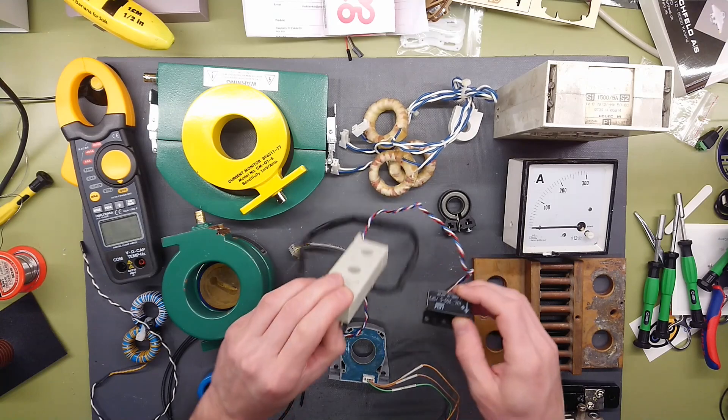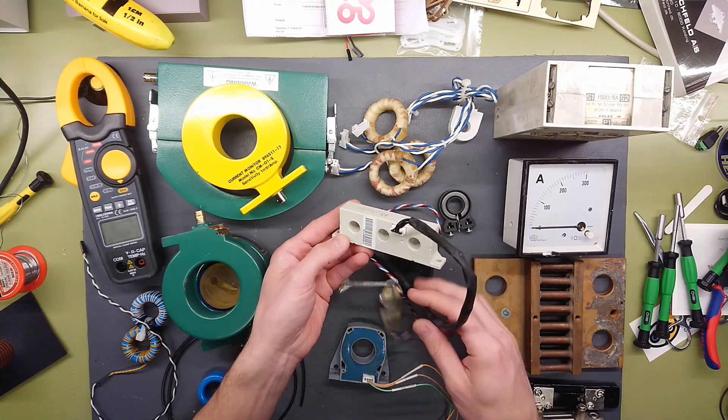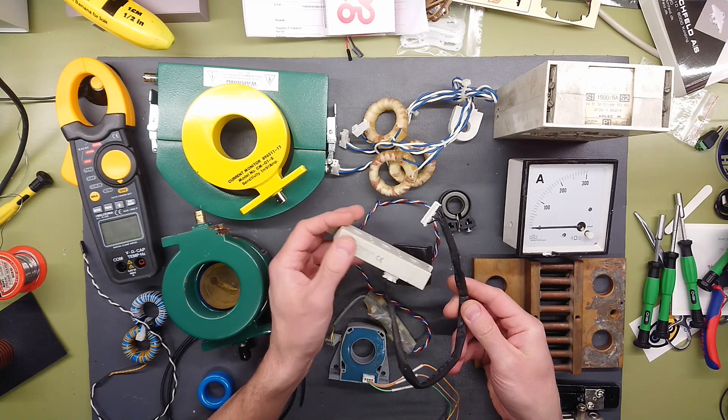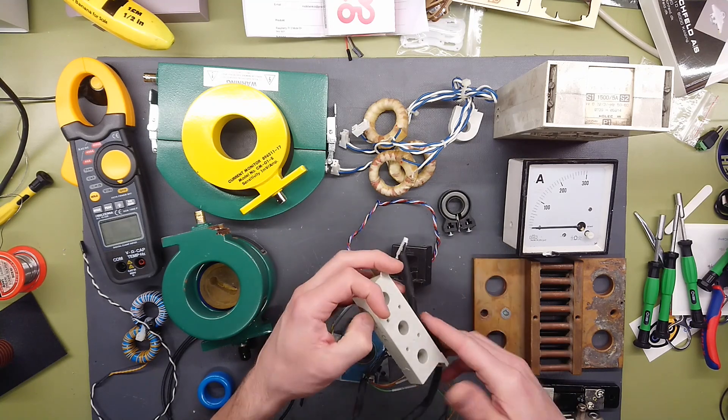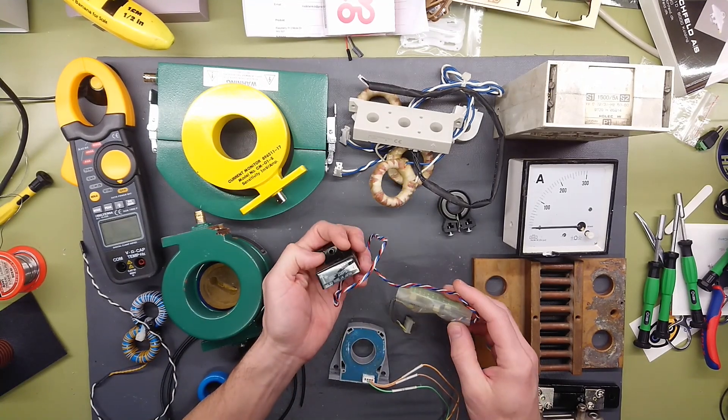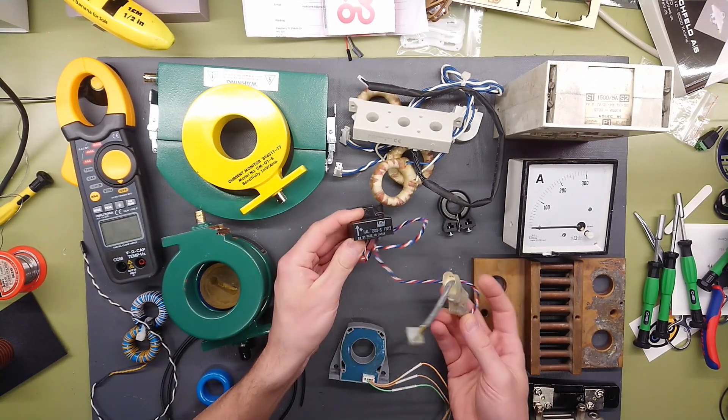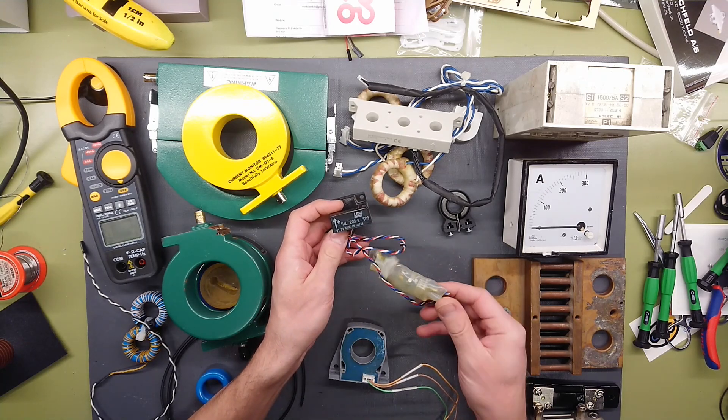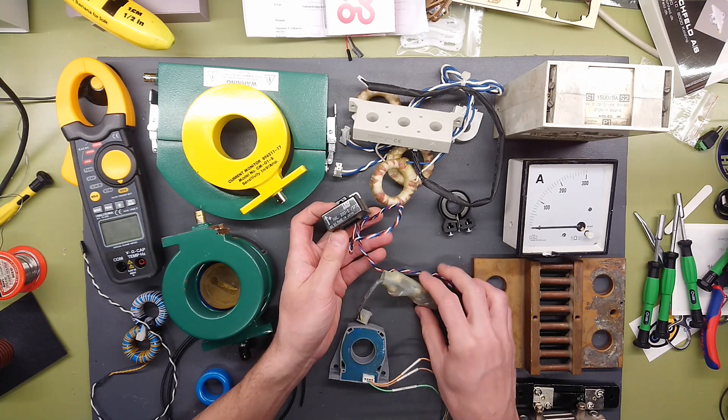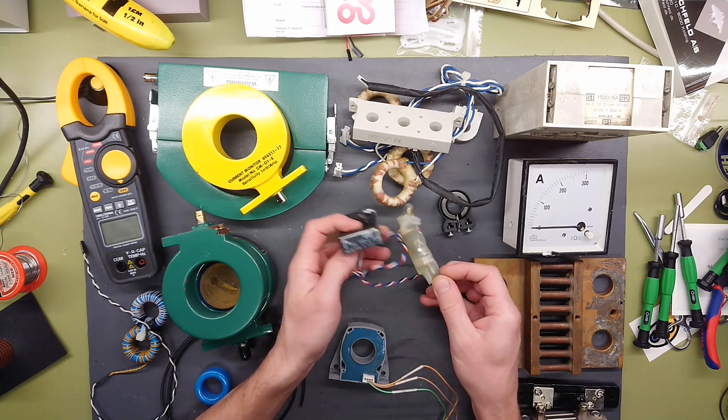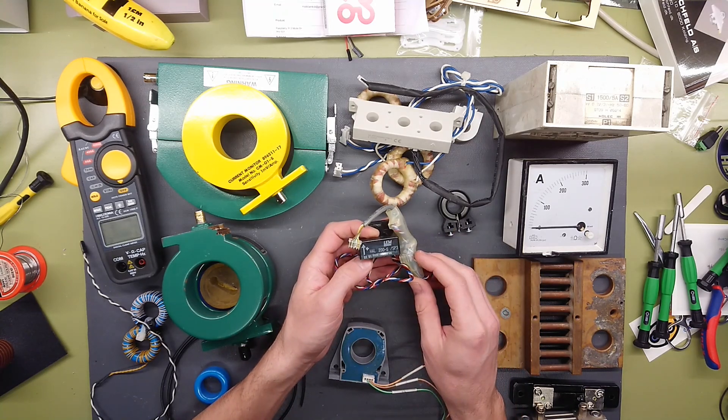Now this comes in all kinds of packages. Here's a three-phase version where it just comes out with a supply and the three signals and some common signal, common ground. You find these LEM sensors almost everywhere you see power electronics. Now this one comes with a small power supply circuit sitting on it so it's probably giving out something like 0 to 10 volt according to the 200 amp rating.